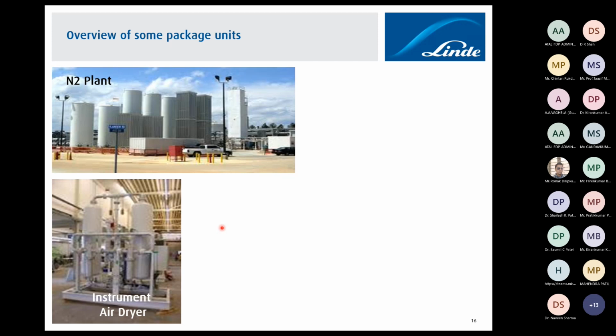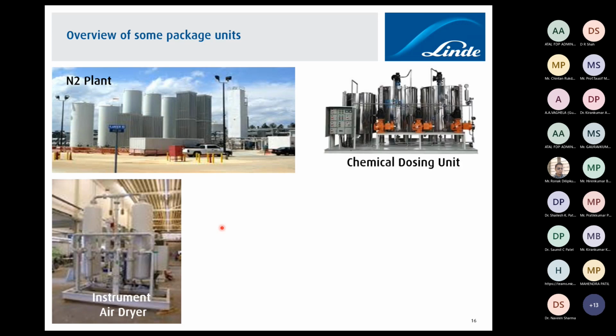But if you look at the scale or a relationship graph, you will see -20 is a pressure dew point. So both are the same. Both have the same air quality, but the measurement has differences. So dew point varies depending on the pressure. This is the key thing when we specify a dryer, or usually when we get such requests, we always clarify the dew point, which condition you need.